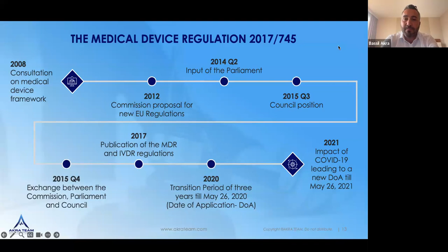Now, one of the important aspects, and I think Kalideep spoke about it during his opening, is the higher obligation and requirement on clinical data at the pre-market level and on clinical data at the post-market level. The MDR includes a lot of sections with additional requirements, starting with the up-classification of some devices, moving to the general safety and performance requirements, which add obligations for devices which are software as medical devices and devices which are connected, for example cybersecurity and so on.